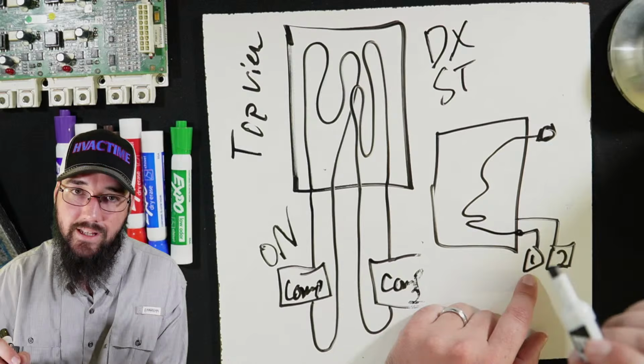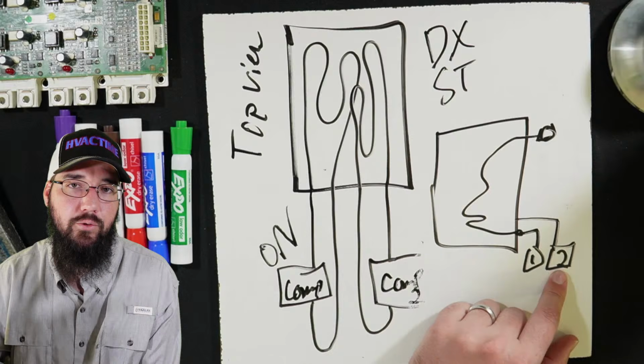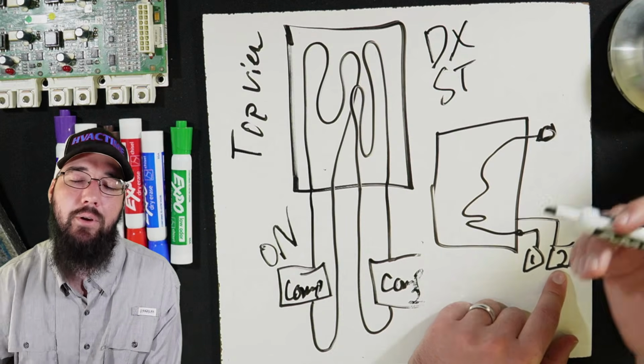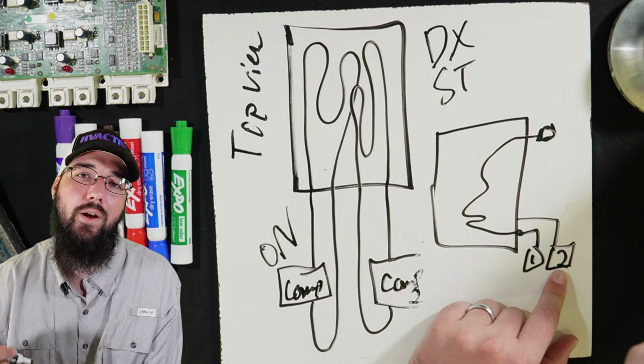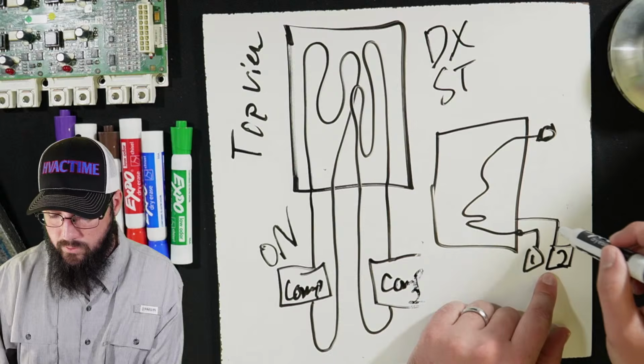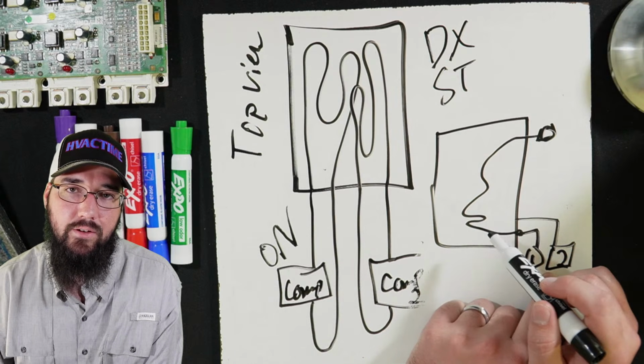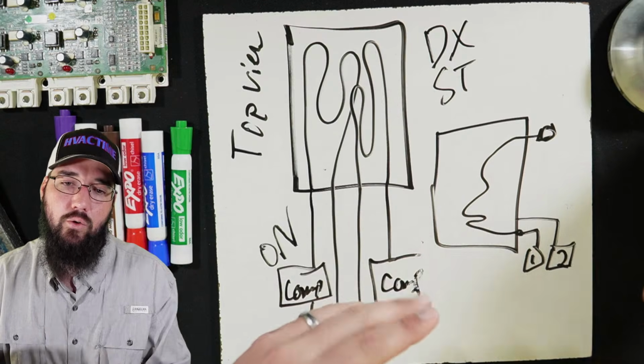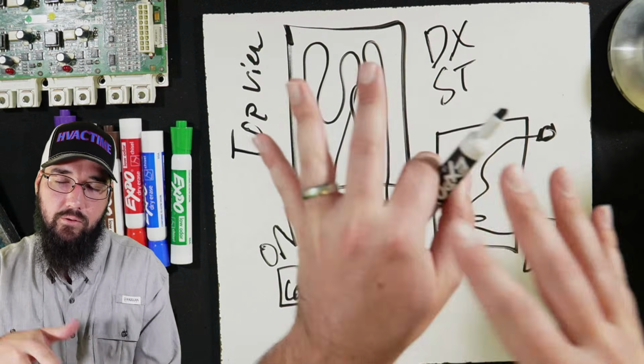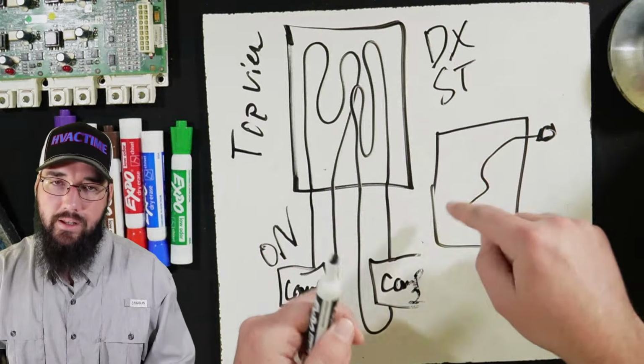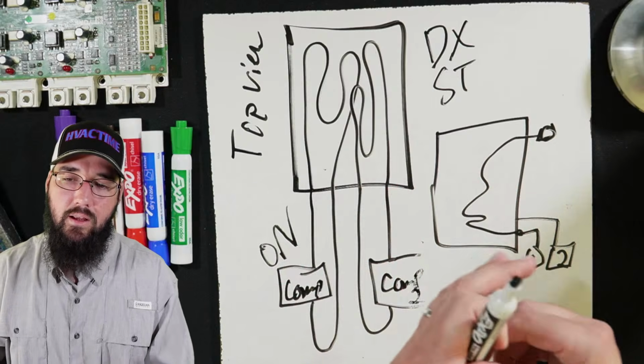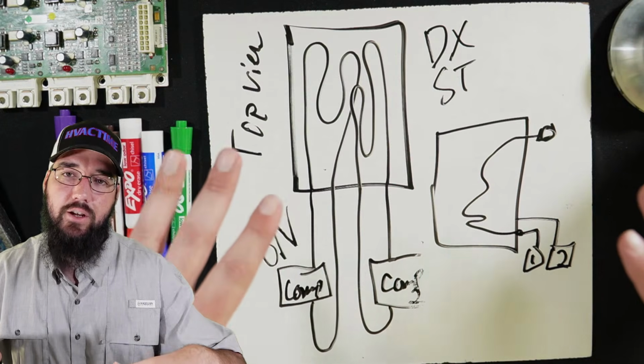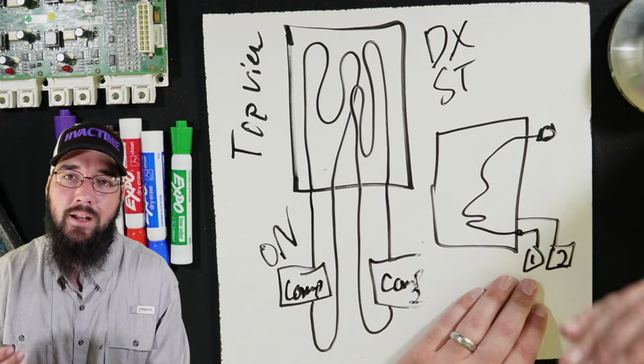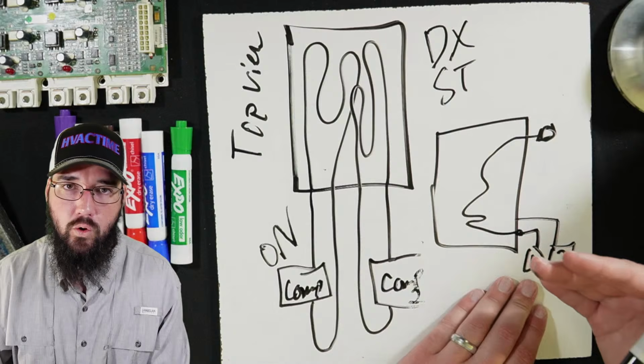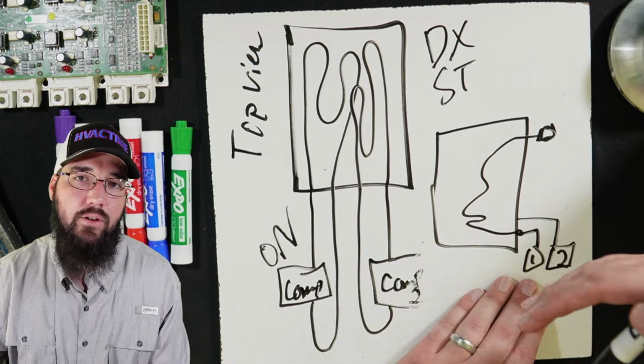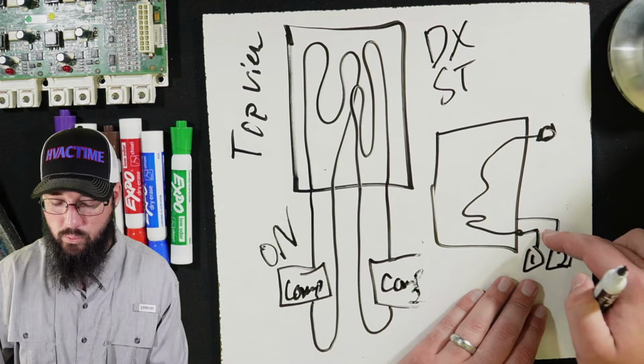But then say the load increases, and we're losing supply air temperature set point. Now we need to bring in the other circuit to pull more heat from the coil. Now both circuits have to share that heat, and they're interlaced with each other, their tubes are all tied into the same fin assembly. So you're going to see the saturation suddenly drop. Not plummet, not in a negative way, but it's going to go to what you would consider normal. So let's say you're running a high 40s to pushing 50 degrees of saturation when circuit 1 is by itself.